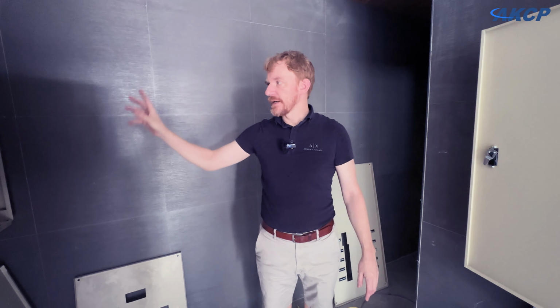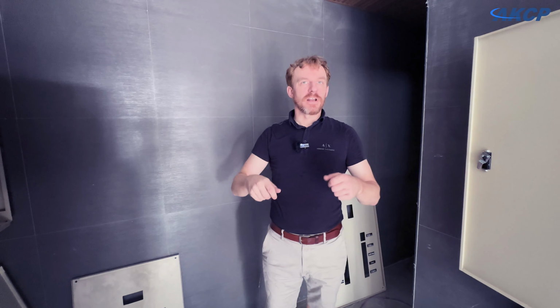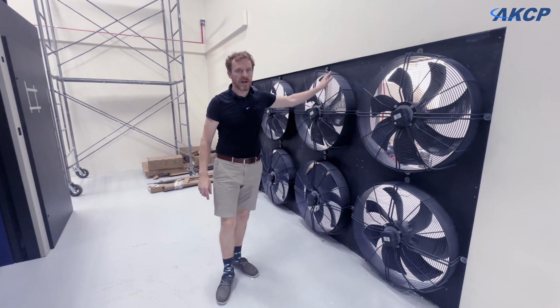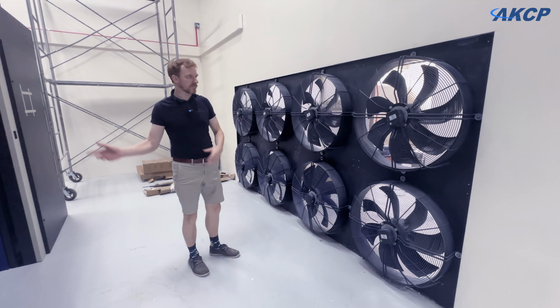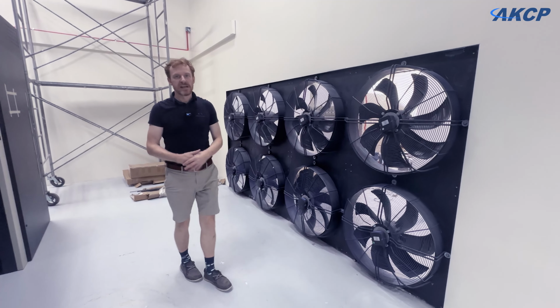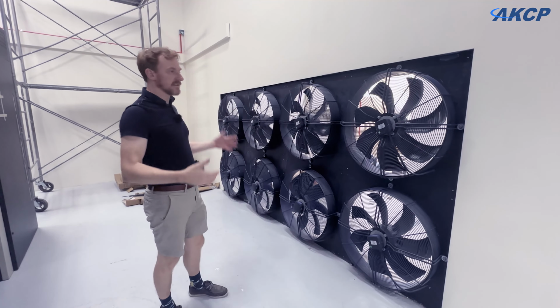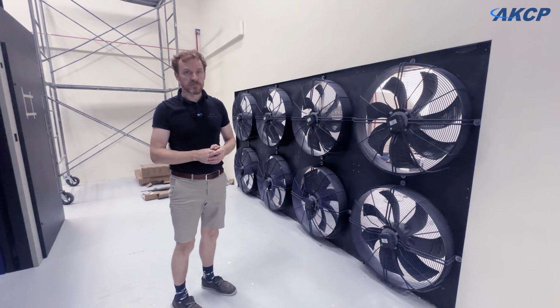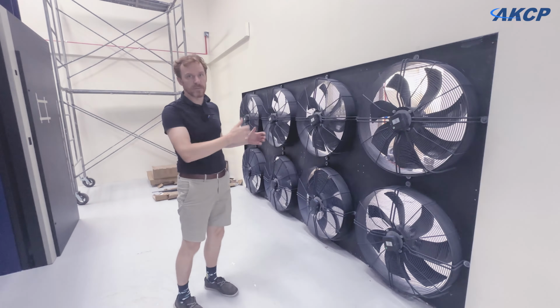Okay, so now we've tested all of the panels. We've made sure that we've got 380 coming into the main breaker on each one. So now we can start doing some of the sub breakers and sending power out to other areas of the data center for us to test those. One of the first things we're going to test out will be the fan wall. We'll make sure that we've got power coming to here and turn these on, and hopefully everything is wired up correctly, and we'll get some air coming out. Fan wall on.